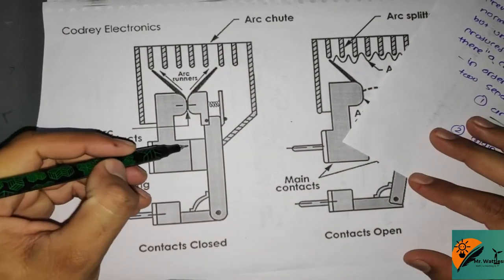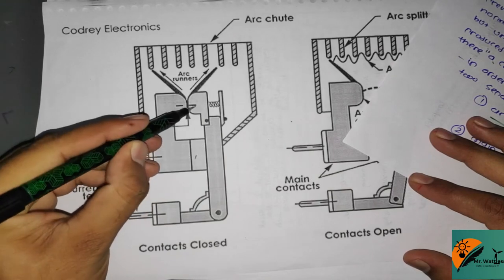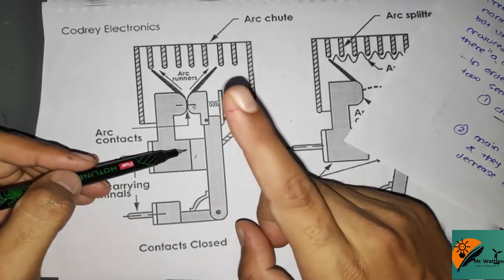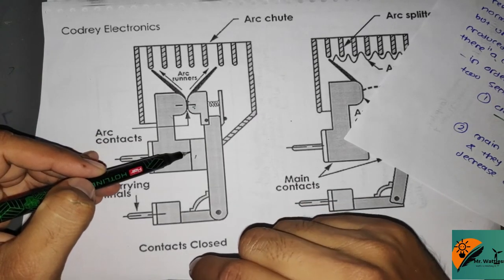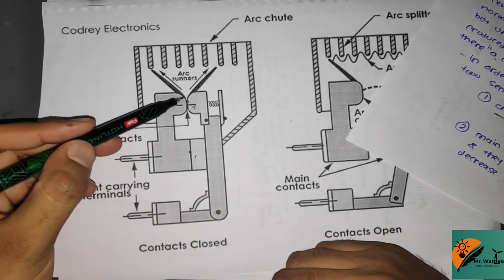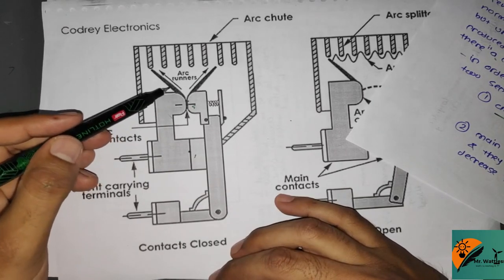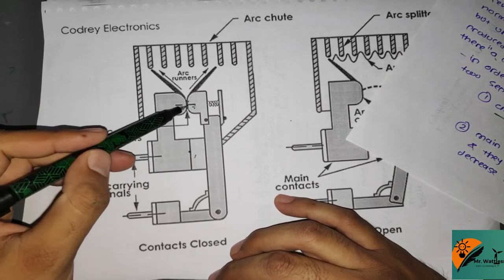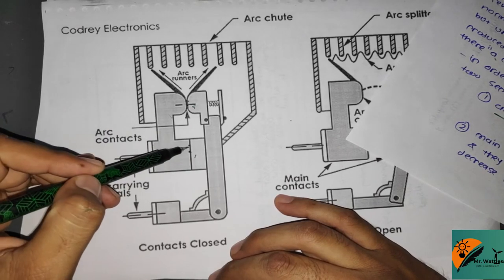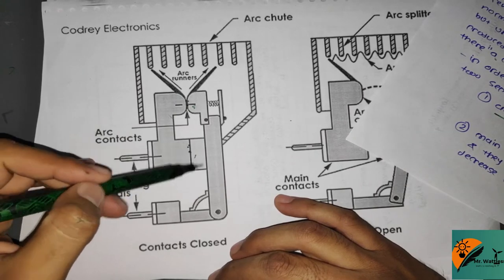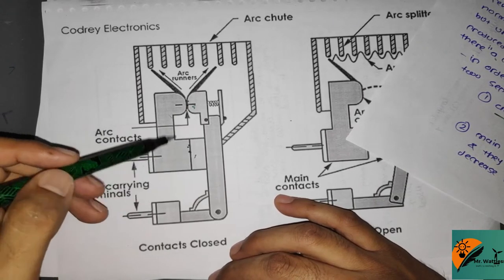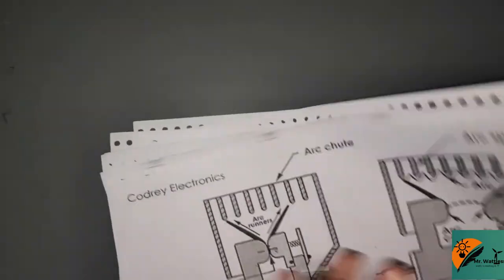In order to avoid damage, contacts are divided into two separate contacts: the first one is the arcing contact, and the other one is the main contact. The arcing contacts are made of copper alloy to withstand more heat. The main contacts are made of copper and plated with silver to decrease contact resistance. So this is the third type of air circuit breaker.